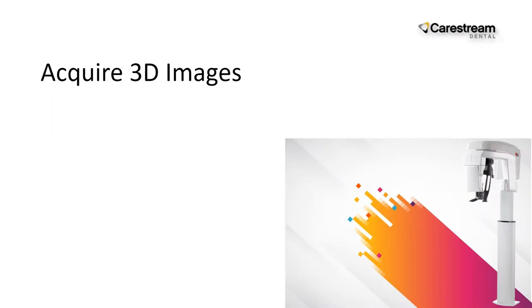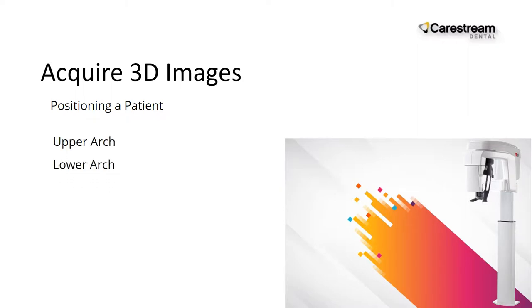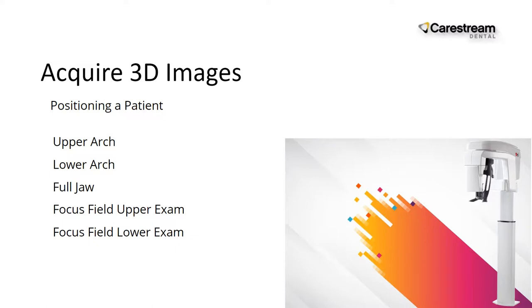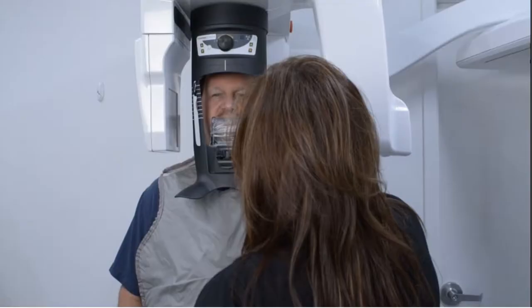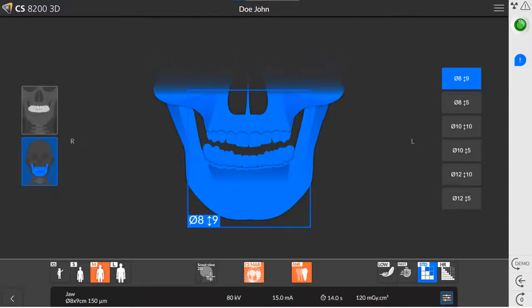Acquiring 3D images — positioning a patient for the following 3D exam types: upper arch, lower arch, full jaw, focus field upper exam, and lower field focus exam. Prepare the unit and the patient, then use the optimized face-to-face positioning system to position the patient. Note: in the patient's history record, any settings used during their first visit are automatically saved. The patient height icon will appear in orange for returning patients.